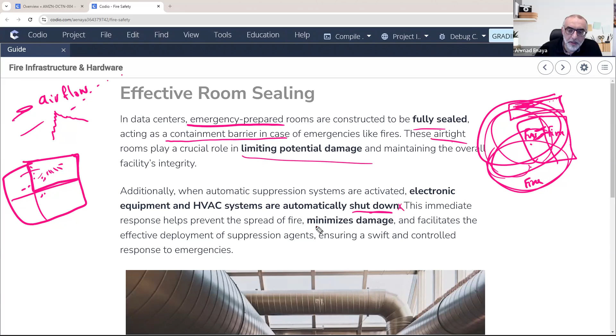And somehow the HVAC should be integrated with this. In case of fire, the HVAC maybe should stop functioning, to make sure that the HVAC is not participating in spreading the fire. Just imagine if you are trying to control the fire, and at the same time your HVAC is circulating the air within the building. Then your HVAC will circulate the fire with the air, and it will be part of the spreading of fire. So the system should be all integrated. There should be a way to shut down the HVAC in case fire is detected. This is to minimize the spread of fire and minimize the damage.